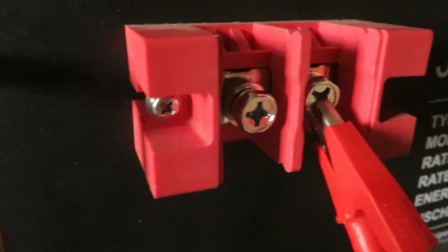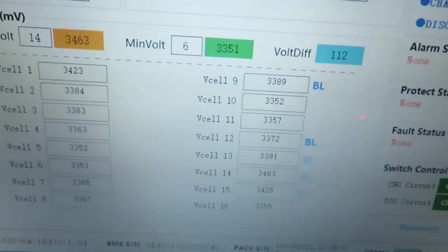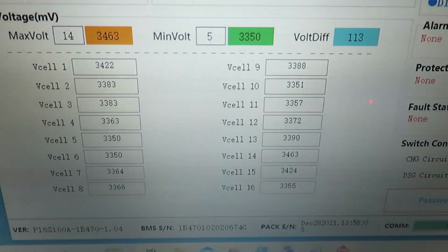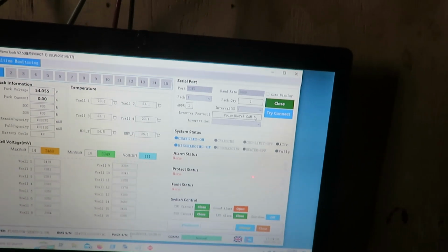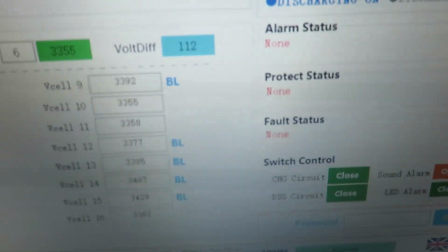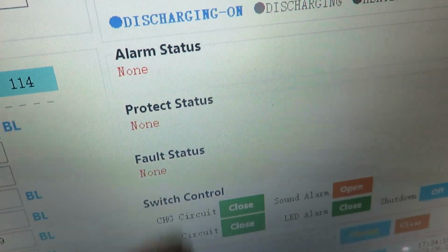Now let me try it. I'll shut off this breaker, which would simulate the BMS is still on. We'll see if it will flip this off. Yeah, there you go, no, they went off. Oh, it hadn't gone into overvolt protection. Turn this back on, turn the charger back on. So the balancing won't stay on until it goes into overvolt protection.